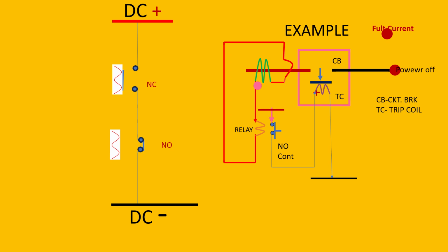Friends, for an example of the use of this contact, I'll show you how a normally open contact, when it makes, extends the DC positive and trips a circuit breaker. So here in the picture, what we are doing is, against a relay normally open contact, in one contact we are giving DC positive, and in the circuit breaker trip coil, which has been shown in green color, the negative is permanently given. But when a fault occurs, the CT secondary is shown in green color also.